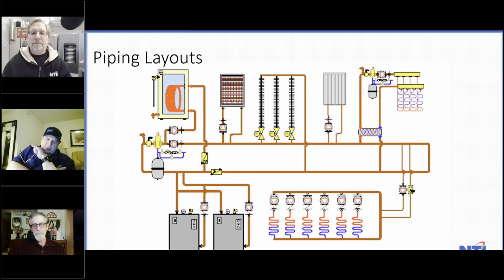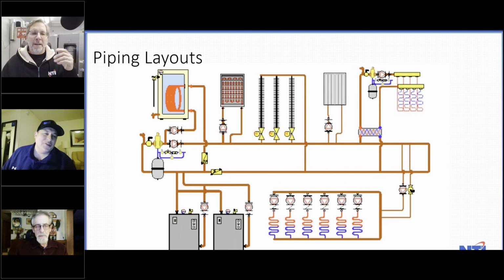Well, I can see those bubbles being very minute at that point coming through that hose. What's that? I can see the air bubbles being minute at that point coming through that hose back into the garbage can. Well, so you suck out of the garbage can, you pump into the system, and you come back to the garbage can with a hose down at the bottom. I really like that idea. When you see no more bubbles, you've properly purged your system. We used to use buckets back in the day when I learned how to purge a system. Yeah, buckets. You weren't using garbage cans. You were using buckets.